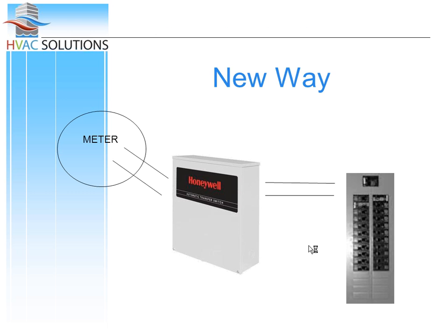The new way, or the Honeywell way of doing generators, is we go from the meter through the transfer switch, and then we back up the entire customer's circuit breaker panel. So if I was to ask you, what is difficult about this installation? You're not standing in front of me, so I'll answer for you. What happens is, if I ask you to turn off power in this situation, you would physically have to pull the meter because there's no switch to turn it off. So the first thing is, you have to pull the meter. And not everybody is capable or willing to do that.